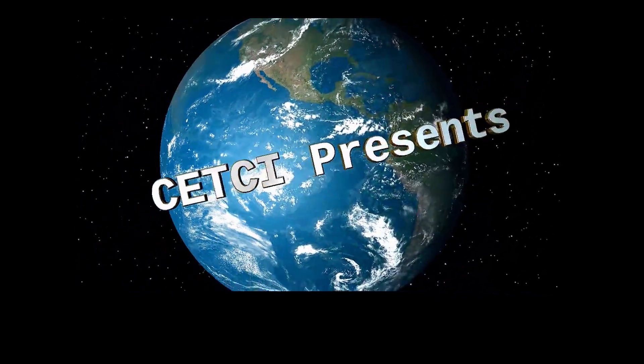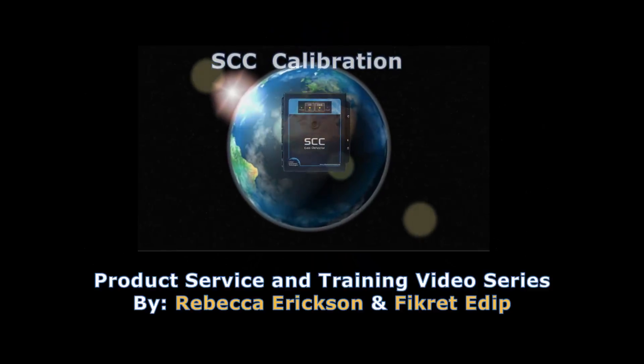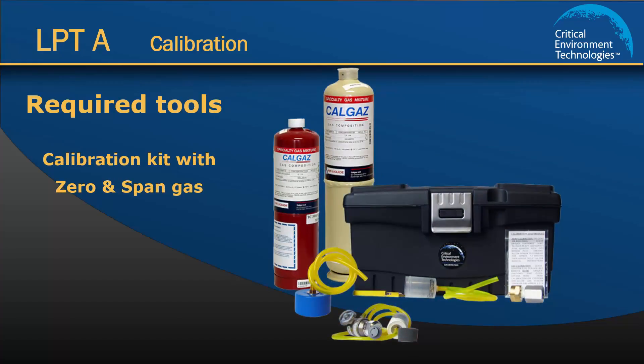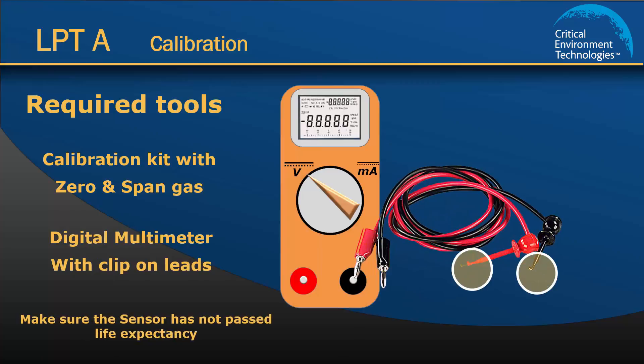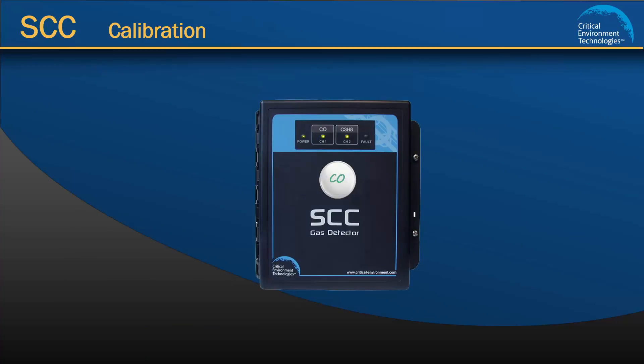Hello and welcome to Critical Environment Technologies video tutorial series: SCC calibration. In this tutorial I will demonstrate the calibration procedure for the SCC self-contained controller. To calibrate the SCC you will need a calibration kit, gas cylinders with a sufficient amount, correct concentration and type of gas, and a voltmeter with hook-on leads. It is also important that you make sure the sensor you are calibrating has not passed its life expectancy. In this demonstration I am using an SCC with one internal CO sensor using channel 1.